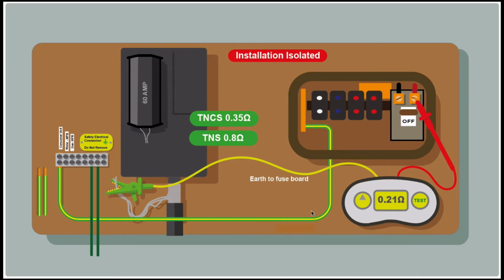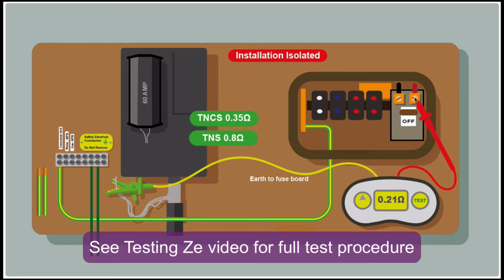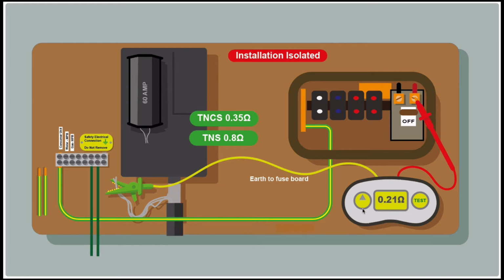So it's a simple enough test. Clamp on the earthing conductor, probe on the incoming live terminal of your main switch, press your button, we get a reading. In this case we've got 0.21 ohms. I'm happy with that. So that's our ZE reading. And I'm happy because it's underneath the maximum, TNS. The maximum is 0.8. You want to be getting less than that, which we have.